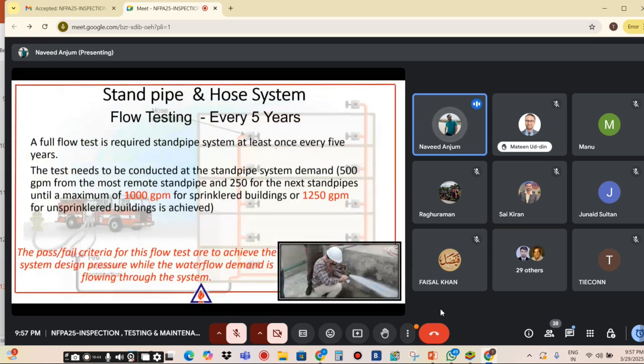And standpipe and hose system flow testing is also required every 5 years. As I am testing here in this picture, you can see me, I am using a pitot tube. We can use a flow meter also, and we can use a pitot tube. So a full flow test is required for a standpipe system at least once every 5 years.